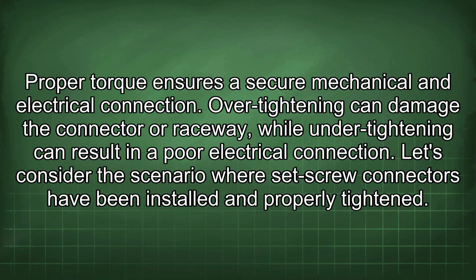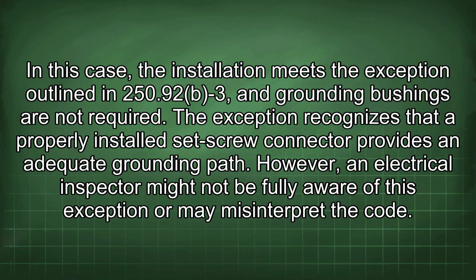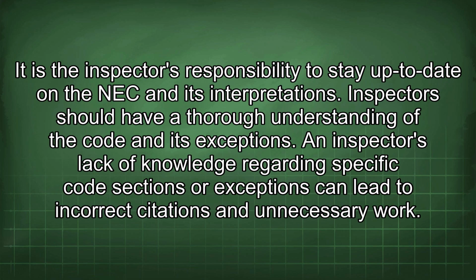Let's consider the scenario where set screw connectors have been installed and properly tightened. In this case, the installation meets the exception outlined in 250.92(b)-3, and grounding bushings are not required. The exception recognizes that a properly installed set screw connector provides an adequate grounding path. However, an electrical inspector might not be fully aware of this exception or may misinterpret the code. It is the inspector's responsibility to stay up to date on the NEC and its interpretations. Inspectors should have a thorough understanding of the code and its exceptions. An inspector's lack of knowledge regarding specific code sections or exceptions can lead to incorrect citations and unnecessary work.